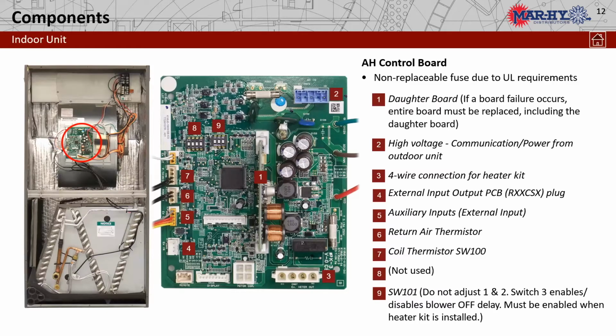This here is our air handler control board. As we can see, number one has a daughter board that plugs into the main PCB. If there's ever a failure with the PCB, you will need to get the daughter board along with it. Number two is our high voltage output, communication, and power from the outdoor unit. Three is your 4-wire connection for your strip heaters. As you look at that, that's the same plug we use on our conventional air handlers, the 4-wire Molex plug-in. The 4 is the external input and output PCB.